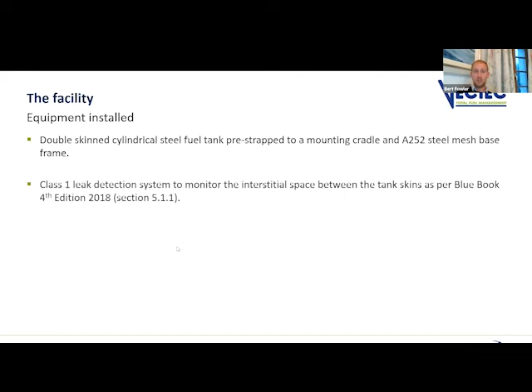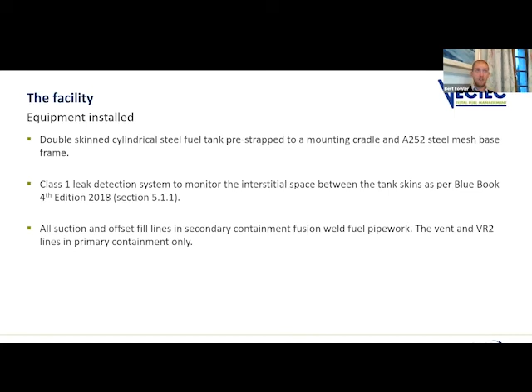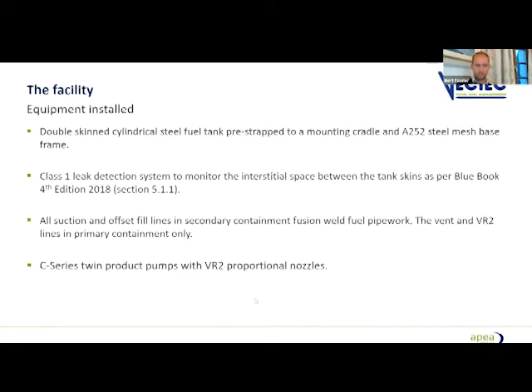There's a class 1 leak detection system on there, as per the blue book, to monitor the interstitial space between the tank skins. Suction and offset fill lines are all secondary containment plastic Durapipe. Vent and stage 2 vapor recovery lines only require primary containment, because they intermittently contain vapor when the tank is being filled or a fueling transaction is happening, but there's no actual petrol in those lines.